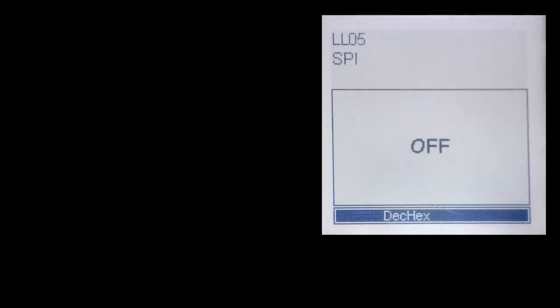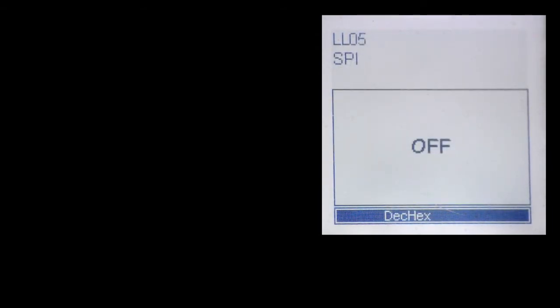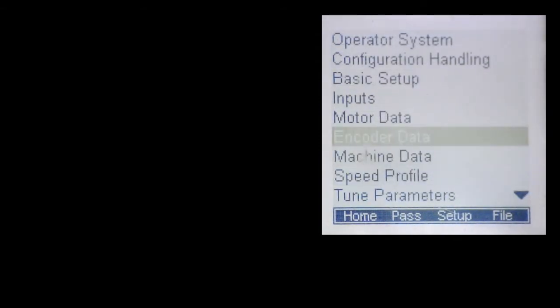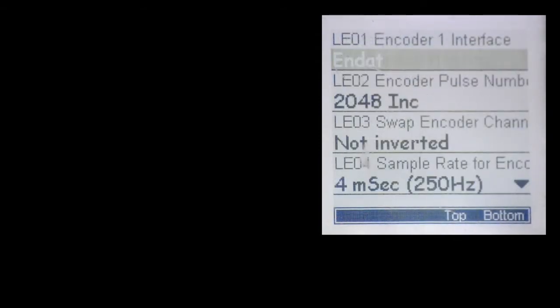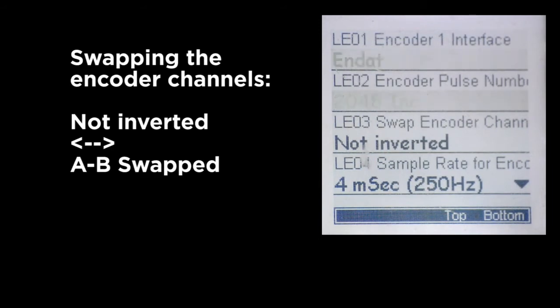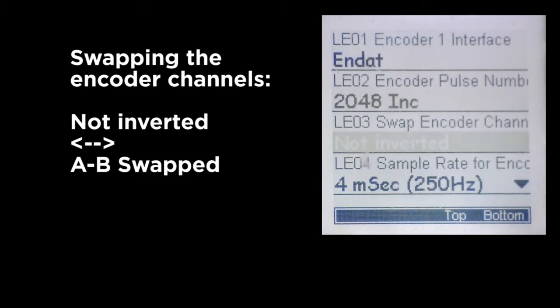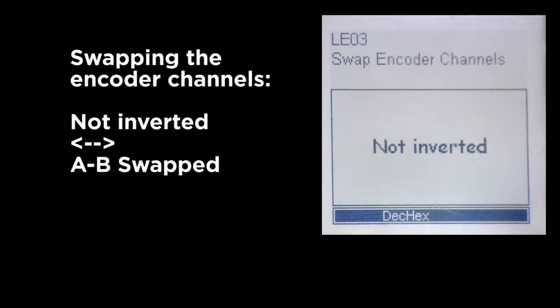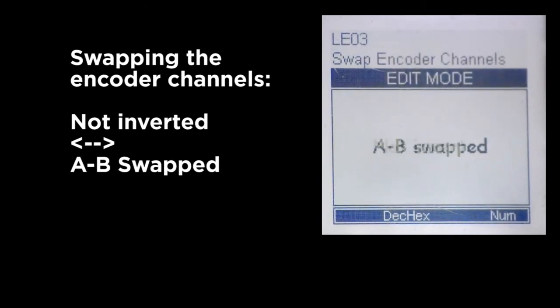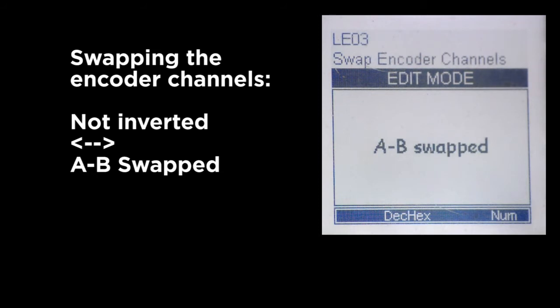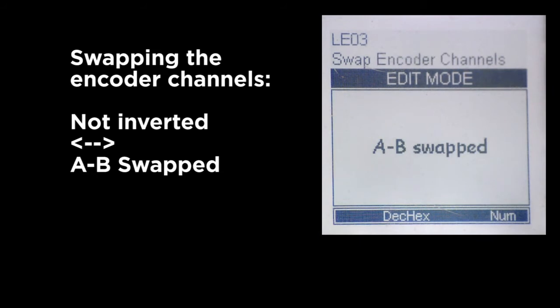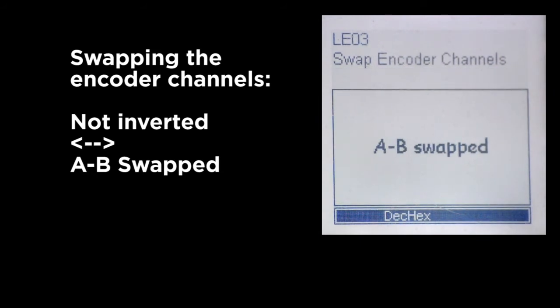As the next step, go to the LE encoder parameter group, parameter LE03. Depending on the current selection, you would either go from not inverted to AB swapped or vice versa. One of the two settings should work.